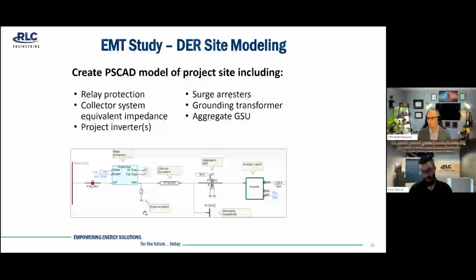If there are any surge arresters contained within the design, we'll model those. Any grounding transformers or other forms of effective grounding like neutral grounding reactors will be included here. And then an aggregate GSU or generator step-up transformer. And same methodology here. If they're all the same GSU, then we'll aggregate them. But if you have a couple of them and they have different windings or ratings, then we'll model them explicitly.